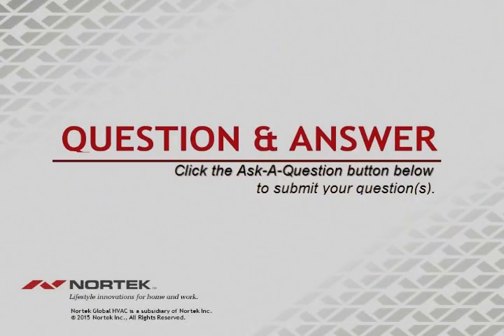$50 is nothing if you take 2 service calls and you have a motor fault and you do the best that you can doing some hopscotch, doing some testing of DC voltage, but you ultimately say, I'm going with a bad motor control board or something like that, and you go back, you get that part, you get it reinstalled into the furnace, and then you still end up with the same issue. That just totally eclipsed the cost of what a motor tester would have been. So I'm always gonna keep plugging away and recommending that motor tester because I think that has good value. Next question.